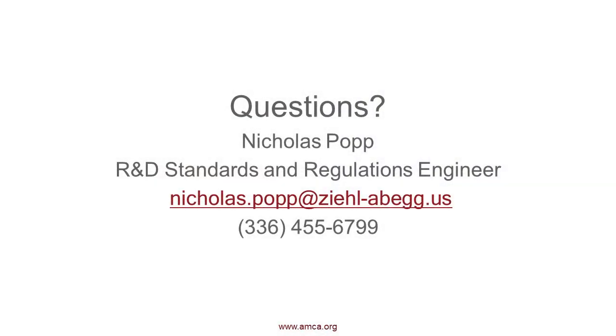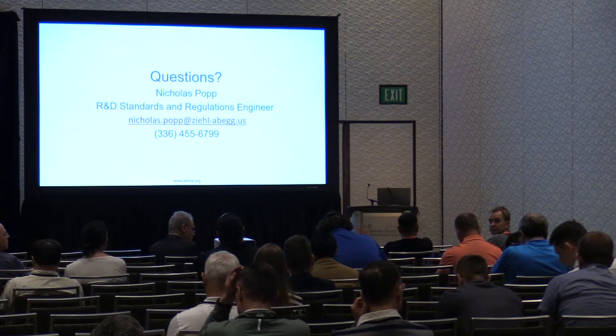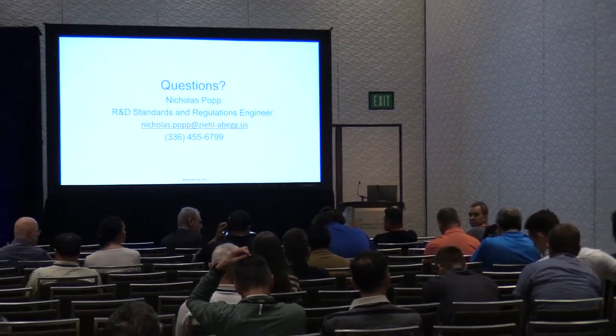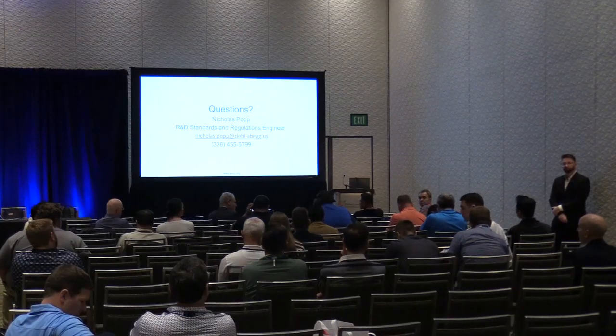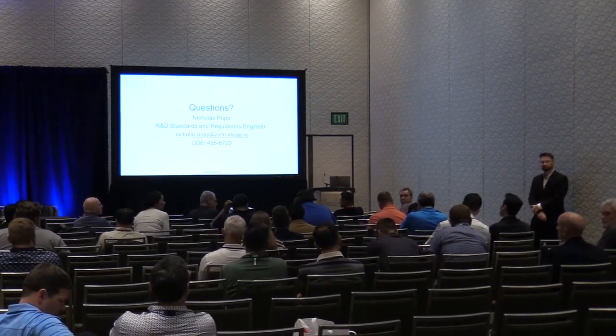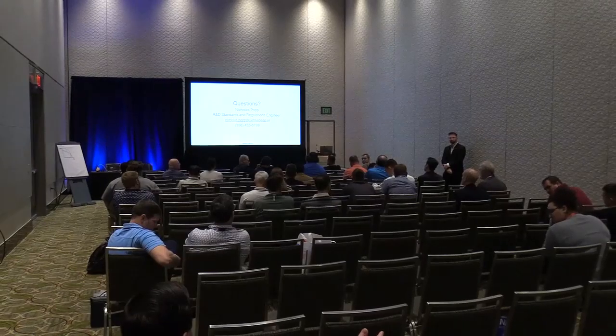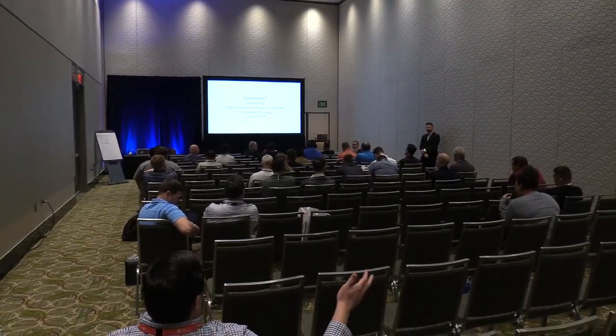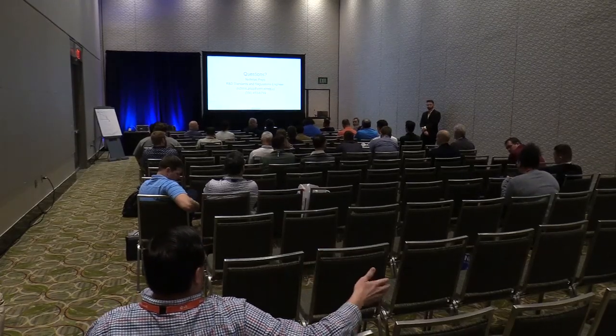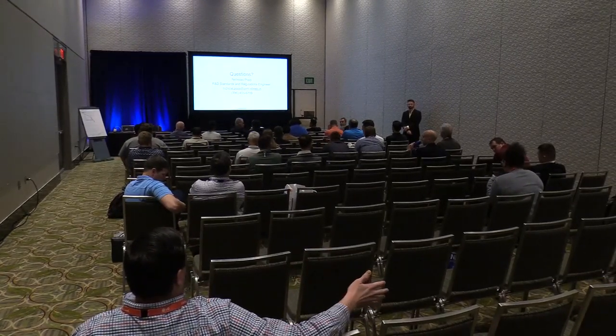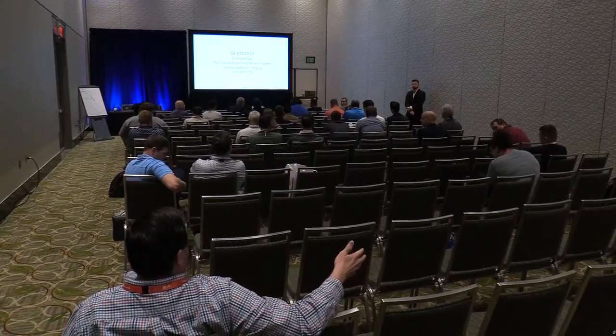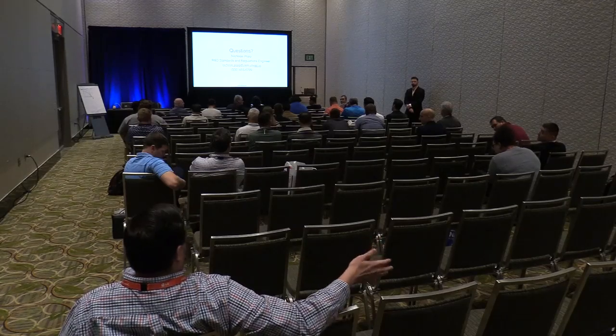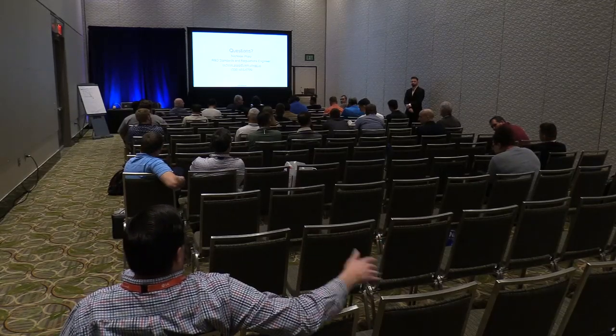At what point do you feel like internal power factor correction becomes the industry standard on certain equipment? On the MEP consulting side, we're dealing with a job right now where they put in four huge shredder motors, and then we get a call asking us to get involved. We're being recommended to put in huge active filters, which is an extremely expensive solution for this site because we have to build a building to house them, since there's no physical space on site. We have to cool and ventilate the space, and these things are huge because they have to overcome these huge horsepower DC motors.